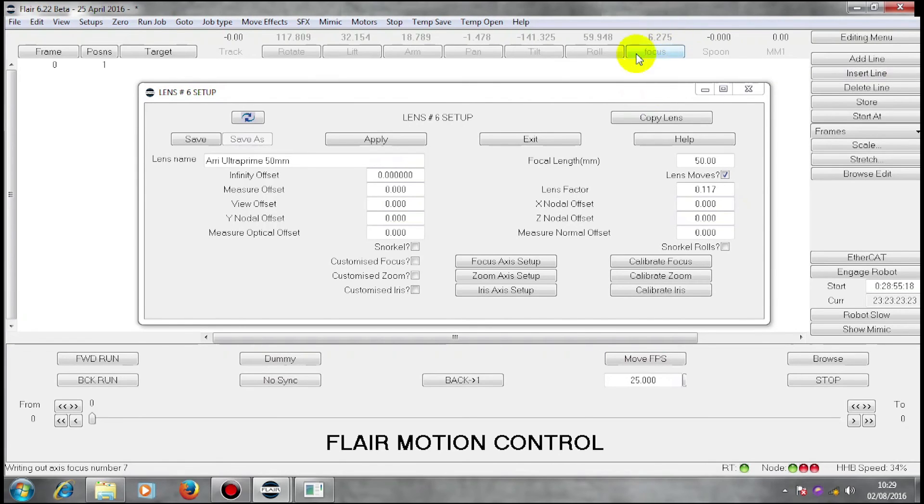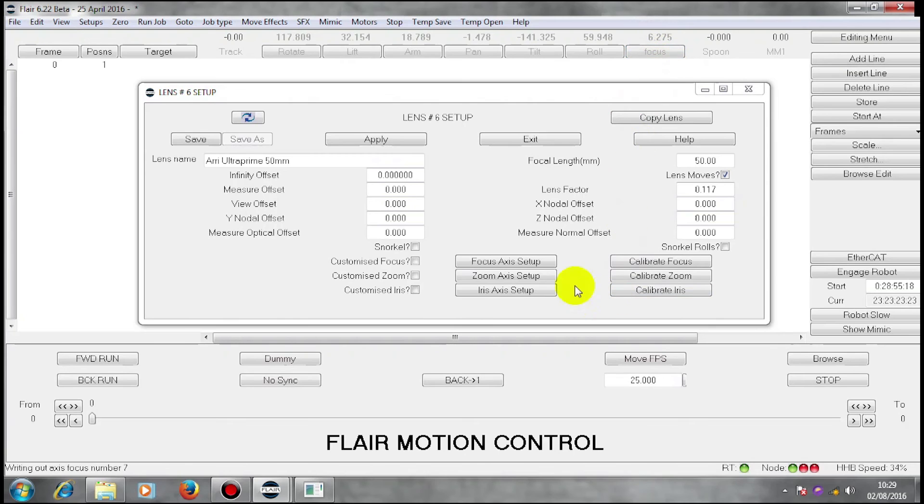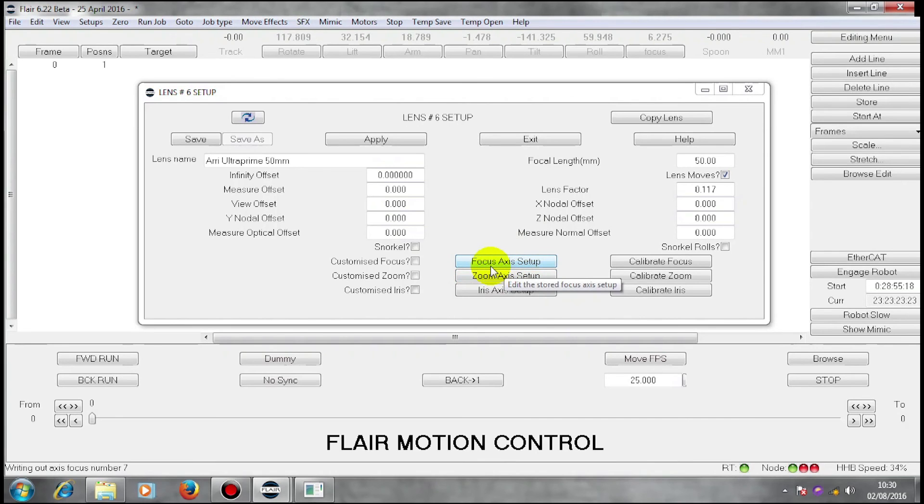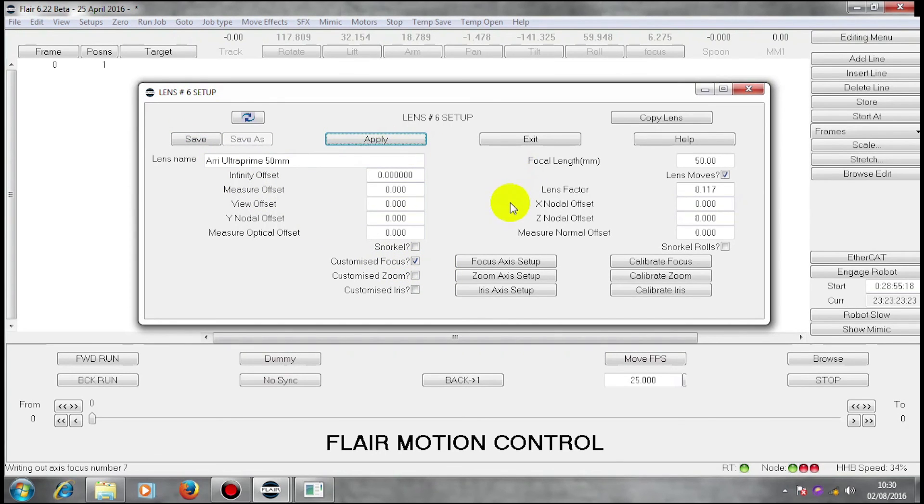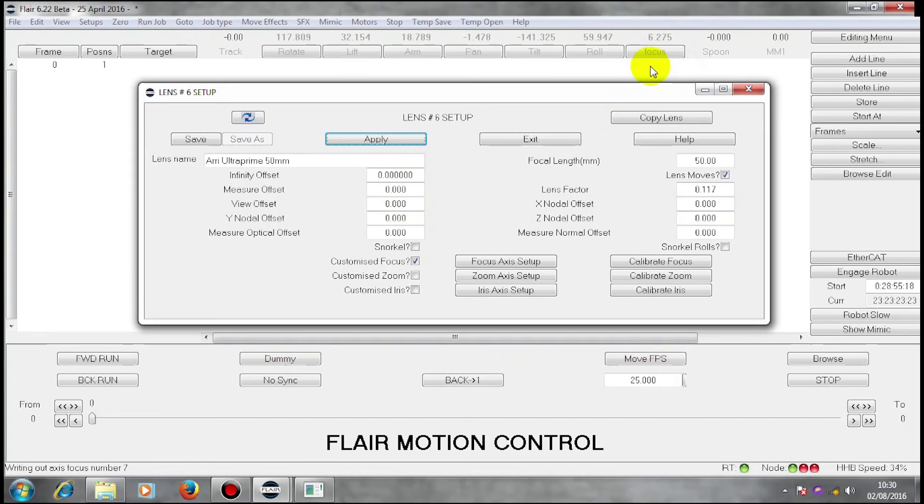In order to be able to come back and use that motor position setup again, I need to store that real information as a library file within this lens. So I'm just going to put my cursor on this button and right click only, which tells me that my current focus axis configuration has been read into my lens setup. Now within here, I have a correct focus axis. So I can now check customized focus. Now when I save, apply this lens, that focus axis will be written over that focus axis.